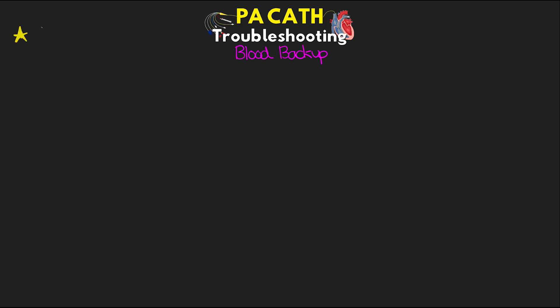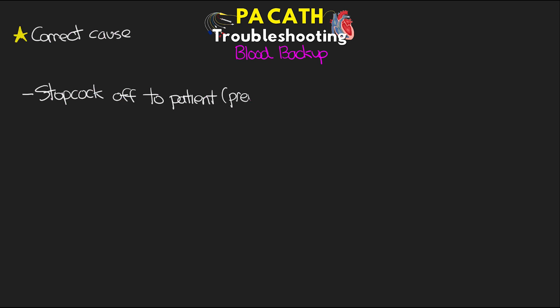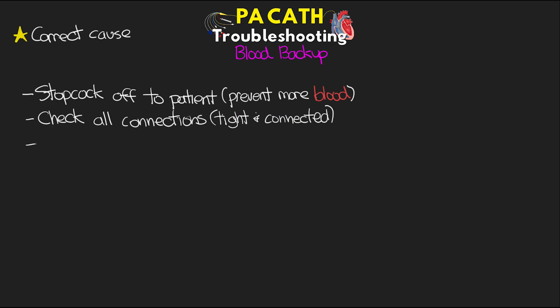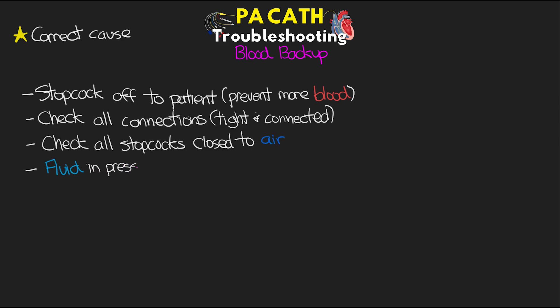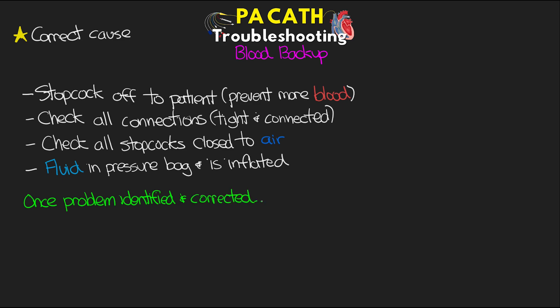The next troubleshooting scenario is when you have blood that's backed up into the PA catheter or the pressure tubing. If you ever notice blood in any part of your PA catheter tubing or pressure tubing, you need to correct the cause. First, turn the stopcock off to the patient to prevent more blood from backing up. Check all your connections to make sure they're tight and connected, and check all stopcocks to make sure they're closed off to air. Ensure that you have enough fluid in your pressure bag and that it is appropriately inflated. Once the problem is identified and corrected, open the system back up to the patient with the stopcock and run a fast flush to get the blood back to the patient and clear your line.